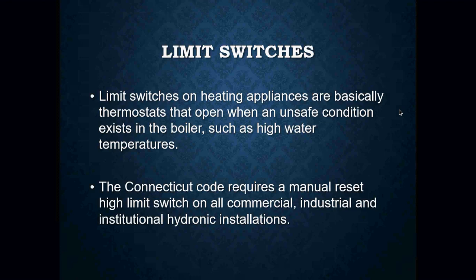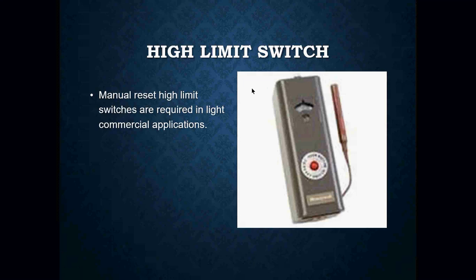Per Connecticut code, all requirements call for a manual reset. Connecticut code requires a manual reset high limit switch on all commercial, industrial, and institutional hydronic installations. Here we have a manual high limit switch — the manual high limit switch is right over here, this little red button right here. Manual reset high limit switches are required in commercial applications.